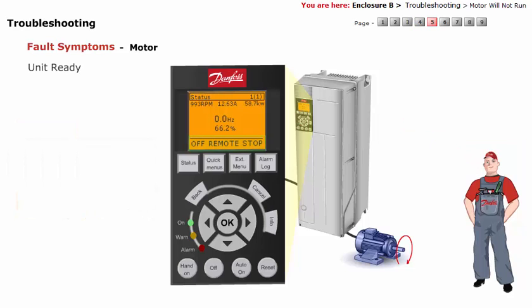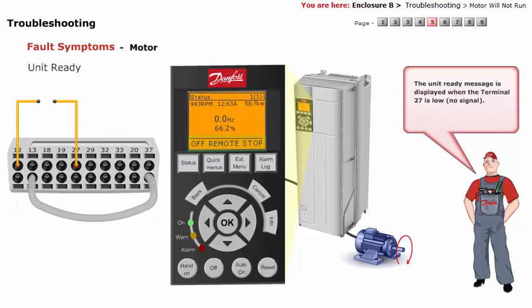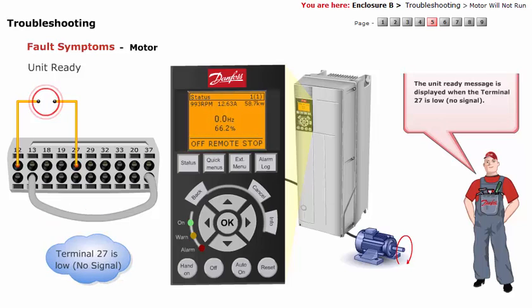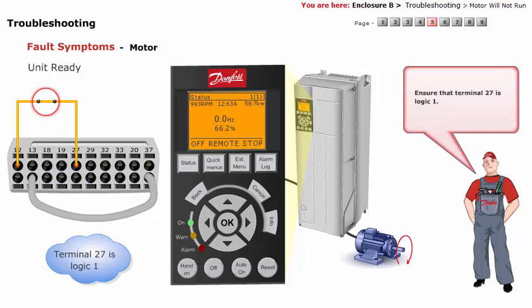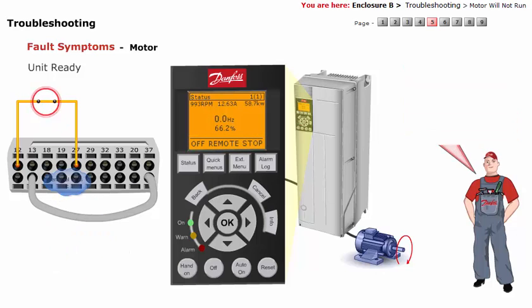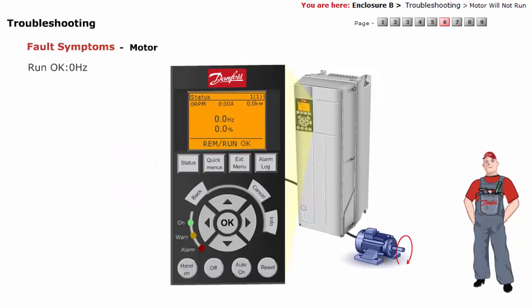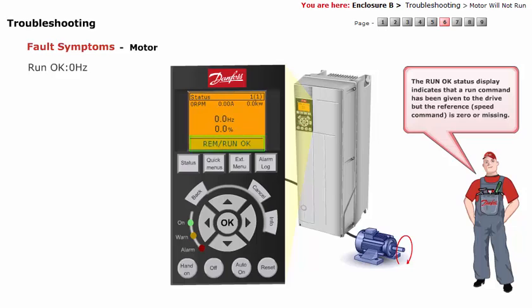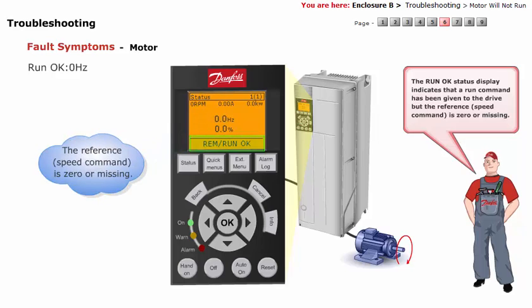Unit Ready: the unit ready message is displayed when terminal 27 is low — no signal. Ensure that terminal 27 is logic 1. Run OK, 0 Hz: the Run OK status display indicates that a run command has been given to the drive but the reference speed command is 0 or missing.